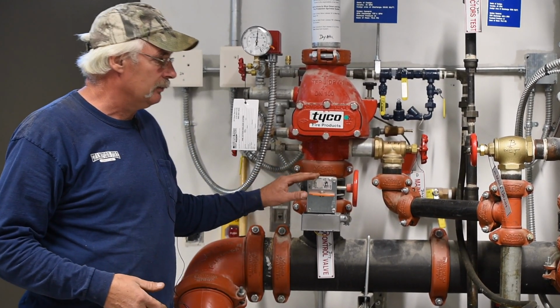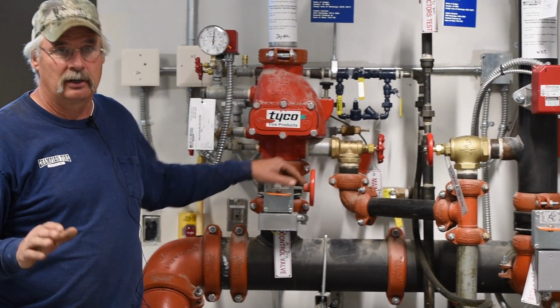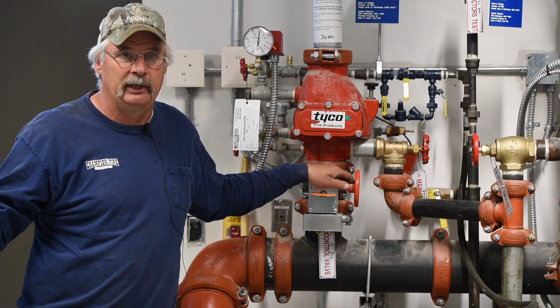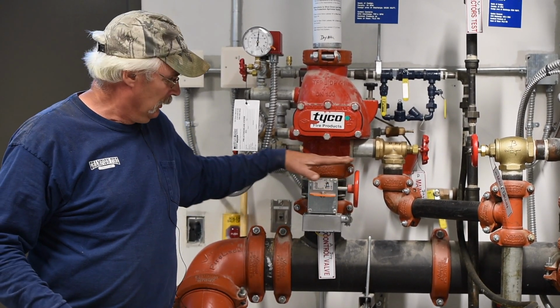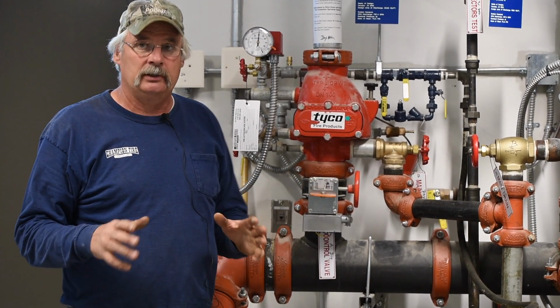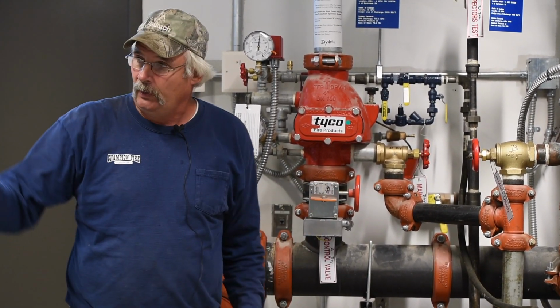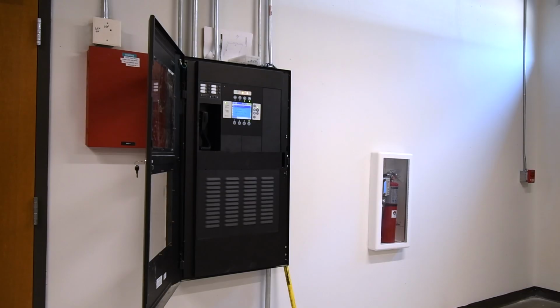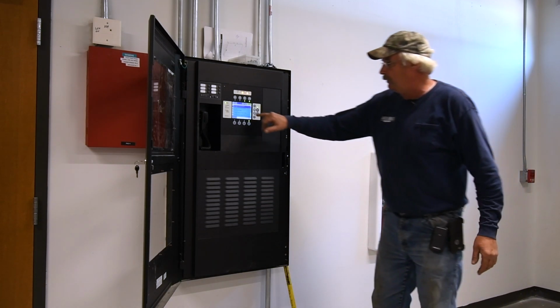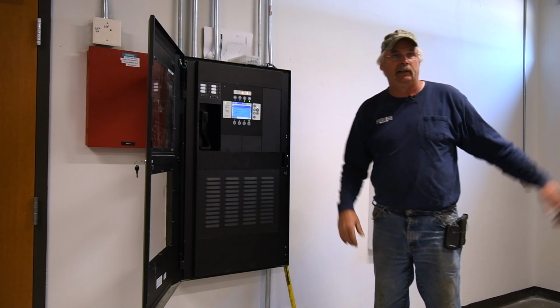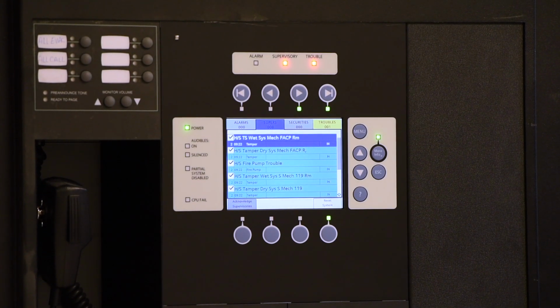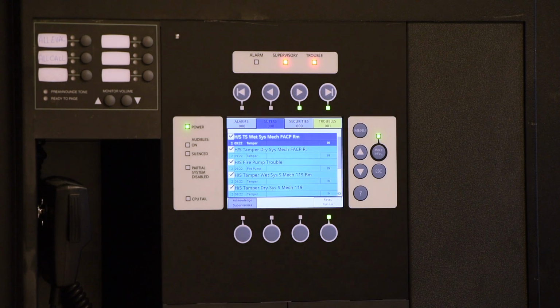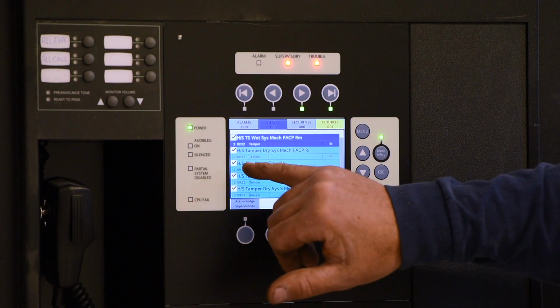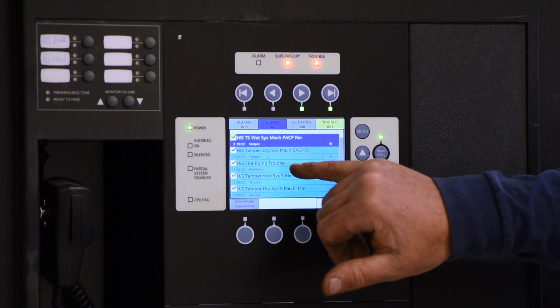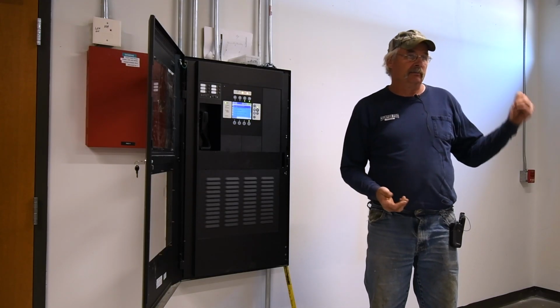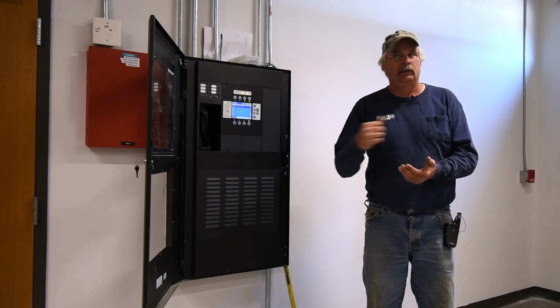So right now, again, all the control valves are off. They're looking for some phone lines to monitor these systems. Once the phone lines get hooked up to that panel, it will report. Right now you'll see a yellow light in your panel, showing that these control valves are shut off in 119 and 158. So 158 would be your north, 119 is your south. And then they also show high school fire pump trouble. We have control valves in the pump house, so it's identifying each area.